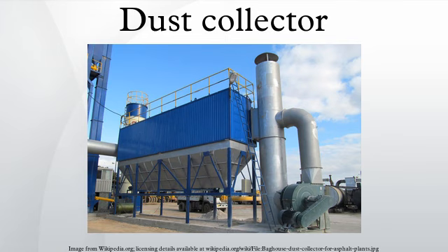Due to its rapid release, the blast of air does not interfere with contaminated gas flow. Therefore, pulse jet baghouses can operate continuously and are not usually compartmentalized. The blast of compressed air must be powerful enough to ensure that the shock wave will travel the entire length of the bag and fracture the dust cake.